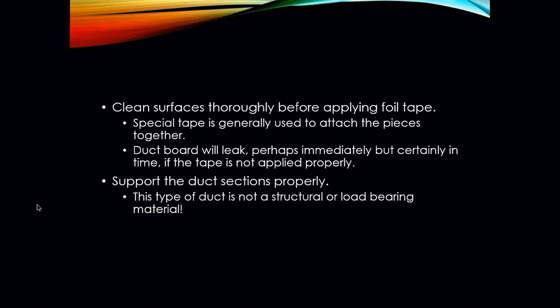To properly clean your fiberboard, you are simply supposed to take a mild soap and water solution and just gently wipe down the area where the tape is going to be adhered. Wipe it down, dry it off, and then apply the tape. Over years, people don't do that anymore. Tape gets applied, it doesn't stick very well, and then over years, the ductboard just starts to leak and finally falls apart. Okay, we have to support the duct sections properly. This type of duct is not a structural or load-bearing material. It will collapse relatively easily.